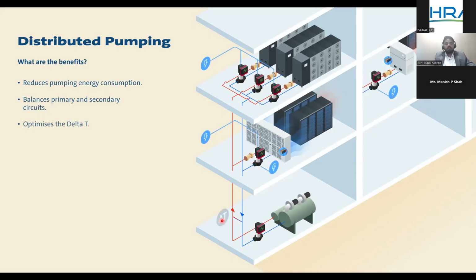As I said, it's optimizing the delta T, which will improve the performance of the chiller, and it's a modular design. When we keep adding CDUs, or fan wall units or CRAH units, the system can be built up as the load grows. So that's the advantage we get when we move to a dedicated or distributed coil pumping system.